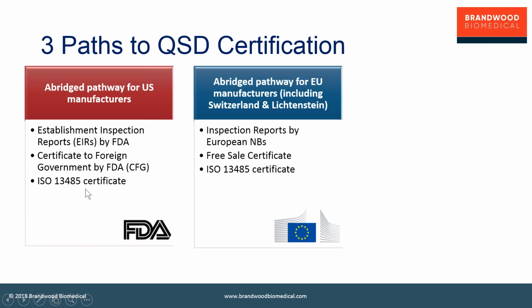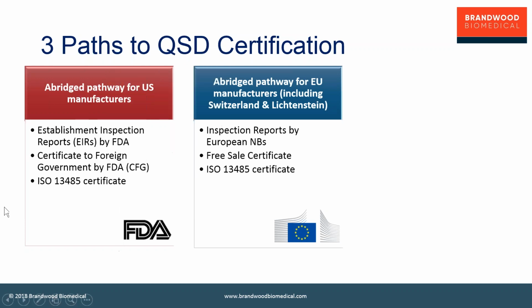The second is an abridged pathway for European manufacturers, including Switzerland and Liechtenstein in the European Economic Area. In those cases, you do a similar thing. You submit your most recent inspection report from the European notified body, you supply a free sales certificate validating that the device is legally able to be sold in Europe, and you supply your ISO 13485 certificate. In each of these cases, you submit this information to the Taiwan FDA, where it's then reviewed, and the QSD certificate is issued based on this information.